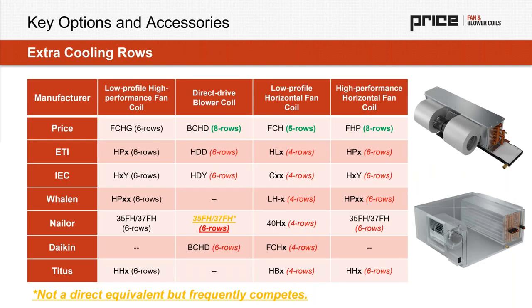Another thing we're doing a little differently with our fan and blower coils at Price is additional rows of cooling and heating wherever applicable. And this really results in energy efficient solutions and cost effective solutions.